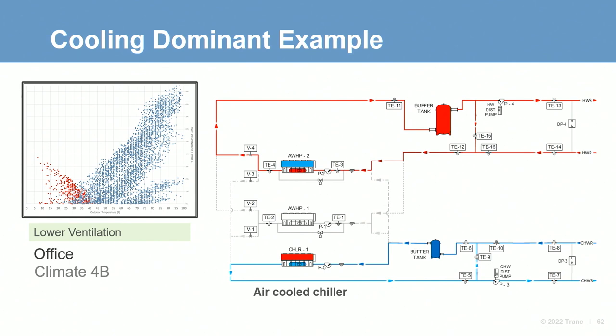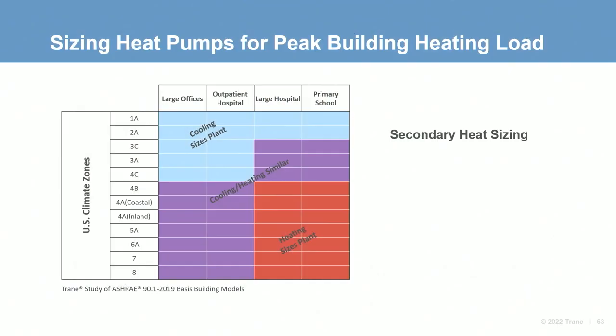This layout also illustrates the versatility of the system. Notice the smaller sized heat pump for the relatively small heating load required, combined with significantly more cooling capacity with heat pumps and chillers. Finally, we need to talk about backup heat. Most air-to-water heat pump technology is limited to about 0 degree ambient. For weather zones where the normal outdoor air temperature drops below zero, auxiliary heat, for example a boiler, needs to be sized to handle the design load.